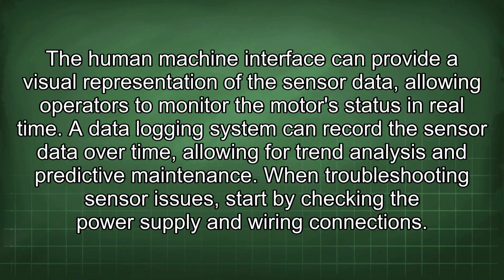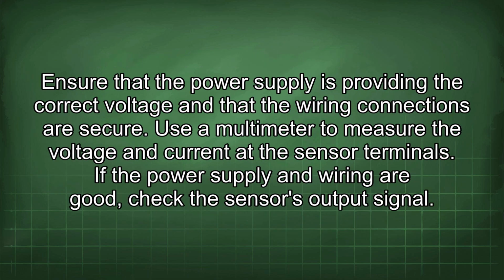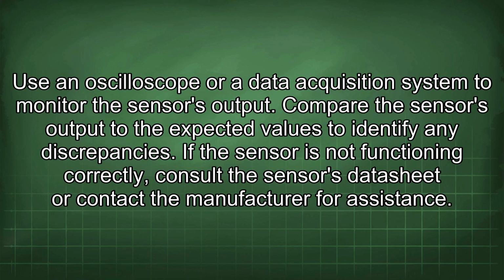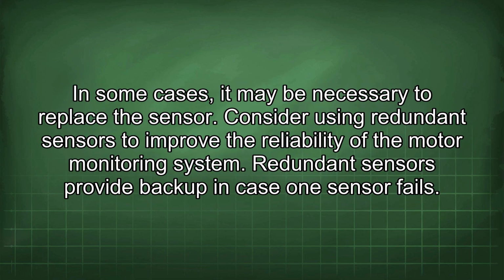When troubleshooting sensor issues, start by checking the power supply and wiring connections. Ensure that the power supply is providing the correct voltage and that the wiring connections are secure. Use a multimeter to measure the voltage and current at the sensor terminals. If the power supply and wiring are good, check the sensor's output signal. Use an oscilloscope or a data acquisition system to monitor the sensor's output. Compare the sensor's output to the expected values to identify any discrepancies. If the sensor is not functioning correctly, consult the sensor's datasheet or contact the manufacturer for assistance. In some cases, it may be necessary to replace a sensor.